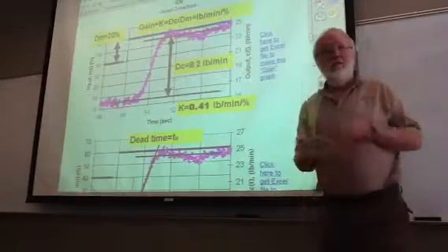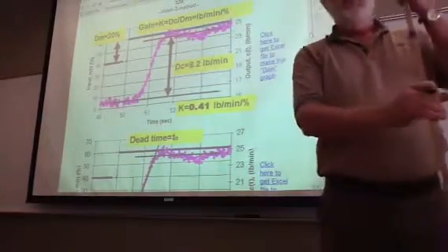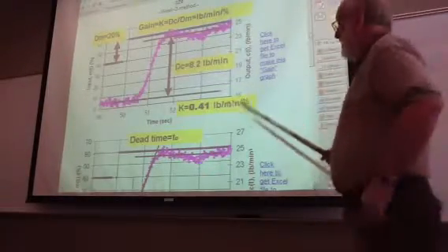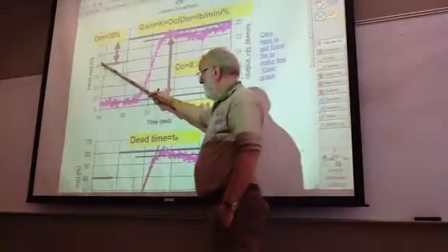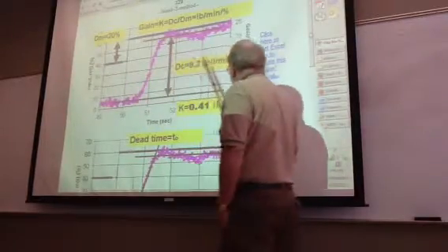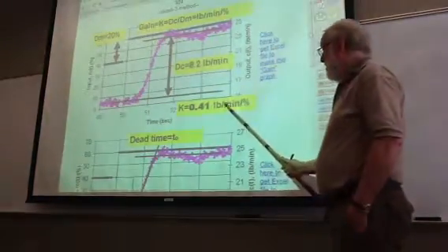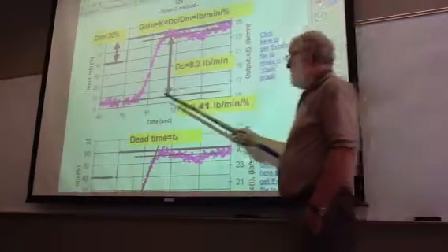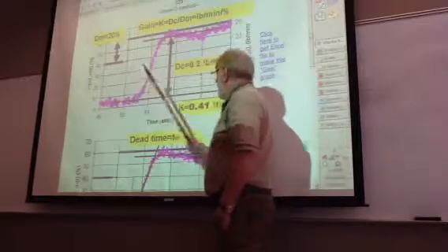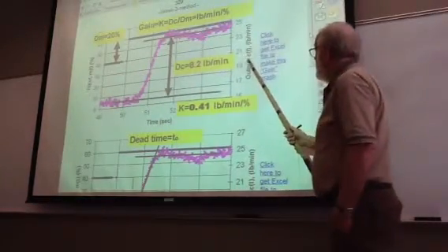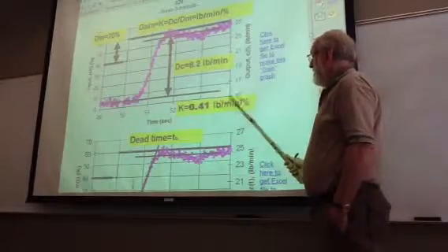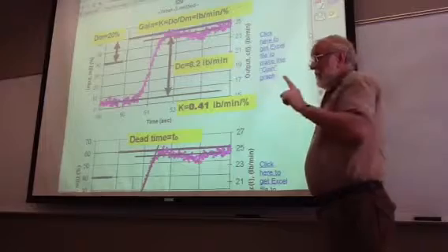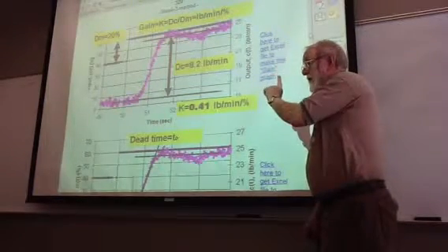How many of you ever heard of units like pounds per minute per percent before? Weird, huh? But that's what it is. If you have temperature, this will be temperature in degrees Celsius, I believe, so the gain will be degrees Celsius per percent. If you have pressure, this will be centimeters of water, so the units will be centimeters of water per percent. So that's the gain based on this experiment. That's one experiment to get the gain.